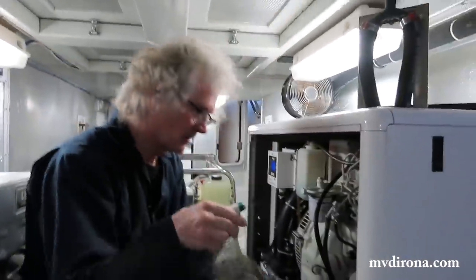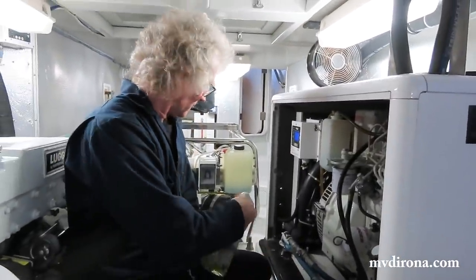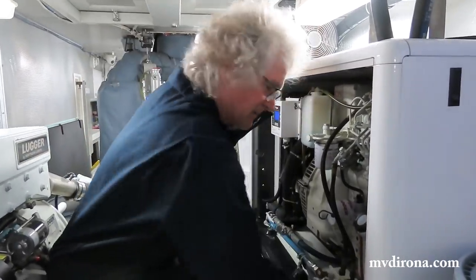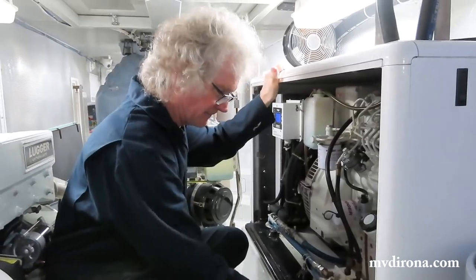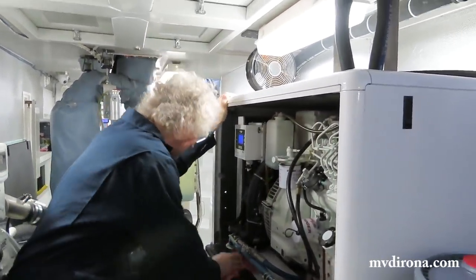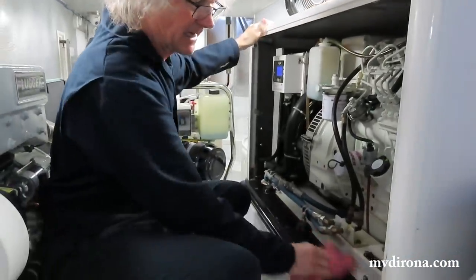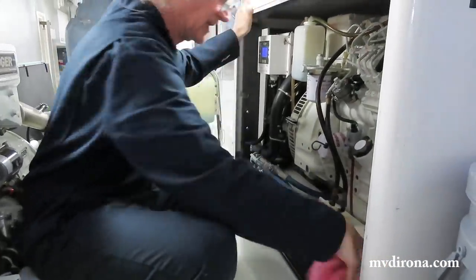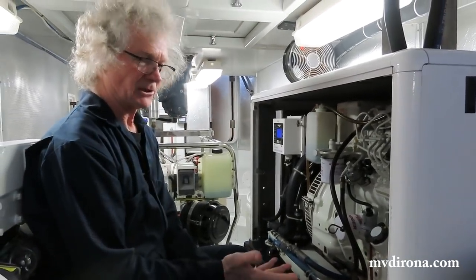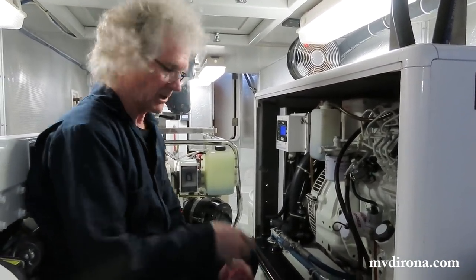That'll give you a fair feel for if it's getting a lot worse as well quickly. Yeah, something like that really shouldn't... You shouldn't really see any bits of water residue underneath a pump like that. And so it says that pump really needs to be changed in the near future. It won't be a catastrophic failure. It'll just start leaking water, is my supposition.